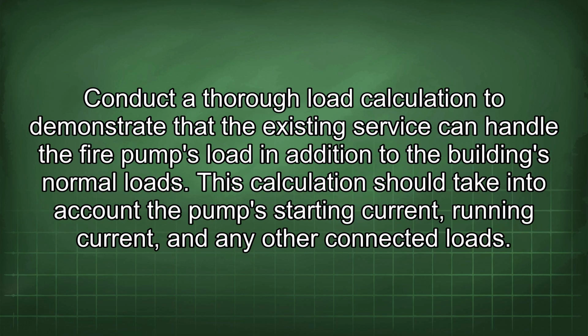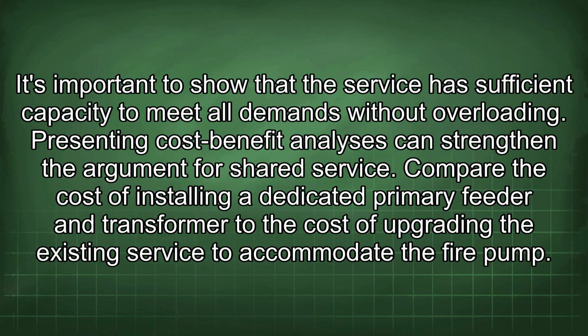Conduct a thorough load calculation to demonstrate that the existing service can handle the fire pump's load in addition to the building's normal loads. This calculation should take into account the pump's starting current, running current, and any other connected loads. It's important to show that the service has sufficient capacity to meet all demands without overloading.